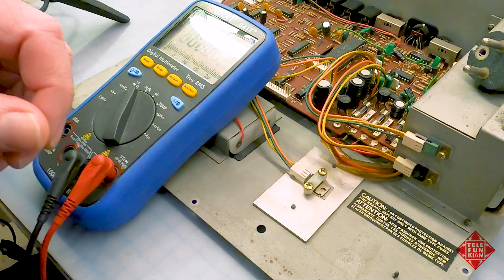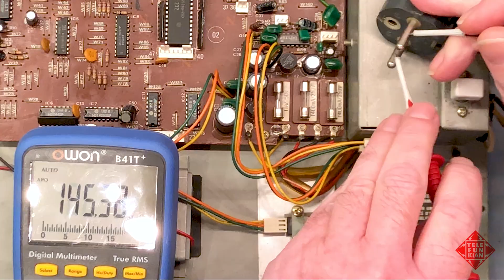Let's dig right in. The first thing I would do is check that power is actually coming from this end of the cable to the transformer. I do that using a voltmeter, measuring across the primary windings of the transformer from this end of the power cable. Doing this, I get an open circuit on my voltmeter. That's not surprising since the power is turned off, so there should be no connectivity between the plug and the transformer - that's what this switch is for. When I close the switch and recheck for conductivity, I still have an open circuit.